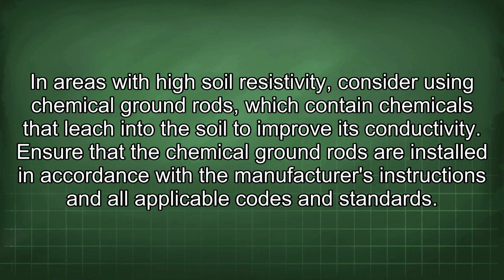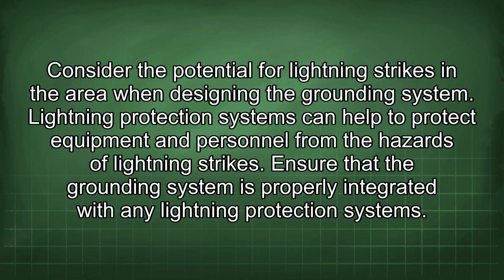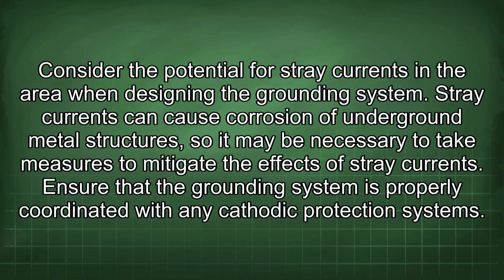codes and standards. Consider the potential for lightning strikes in the area when designing the grounding system. Lightning protection systems can help to protect equipment and personnel from the hazards of lightning strikes. Ensure that the grounding system is properly integrated with any lightning protection systems. Consider the potential for stray currents in the area when designing the grounding system. Stray currents can cause corrosion of underground metal structures, so it may be necessary to take measures to mitigate the effects of stray currents. Ensure that the grounding system is properly coordinated with any cathodic protection systems.